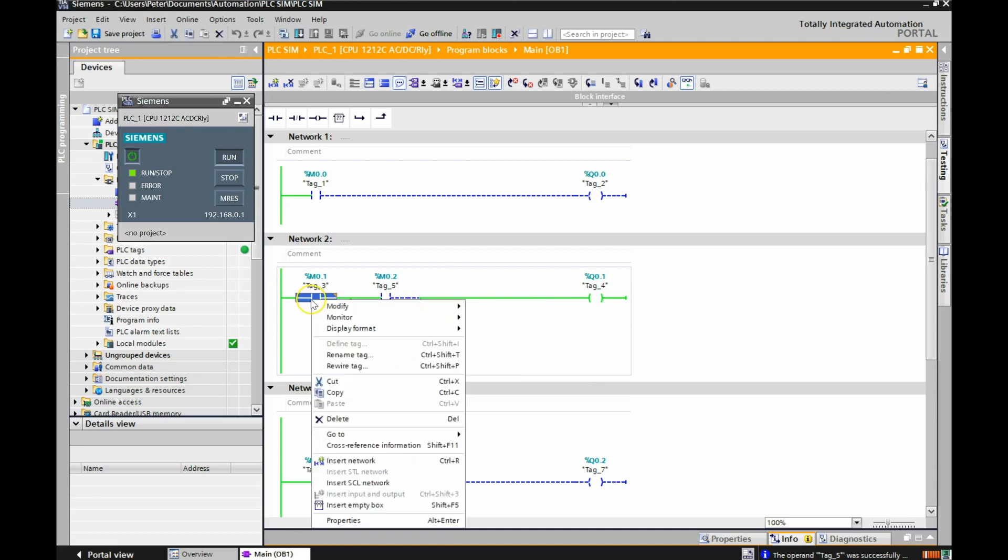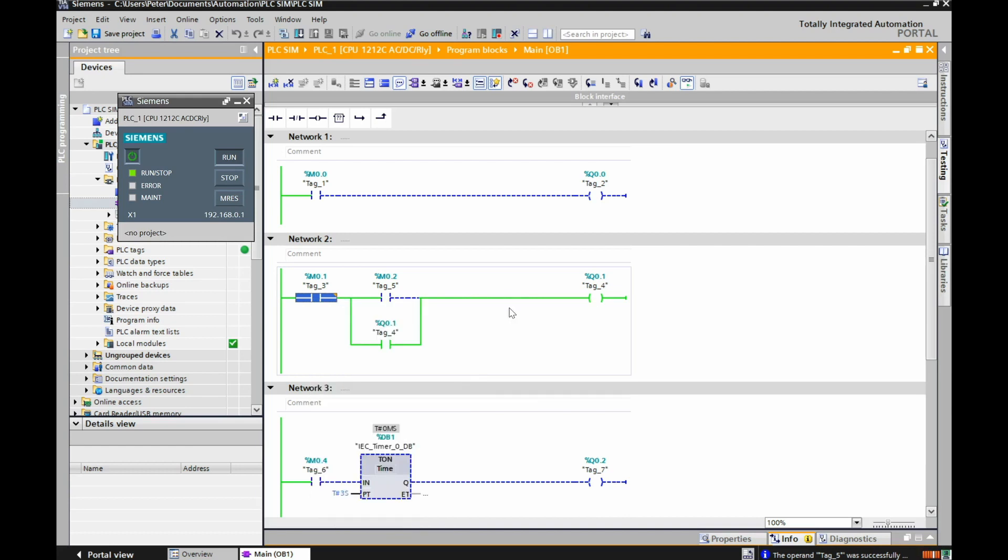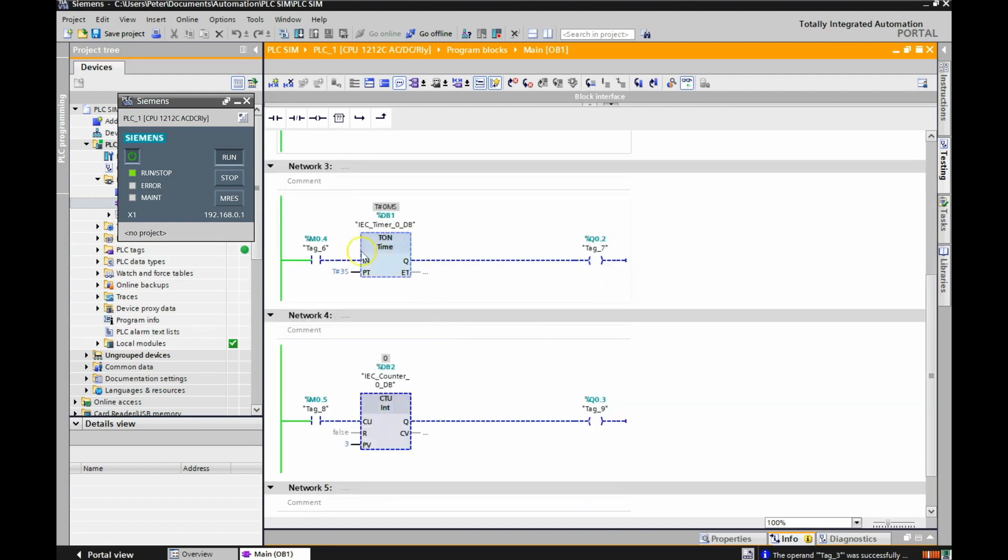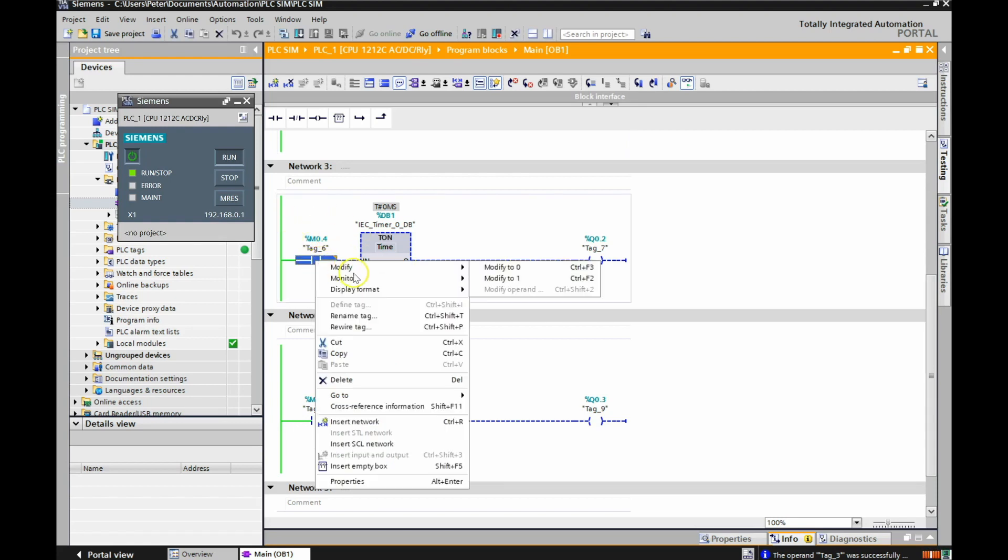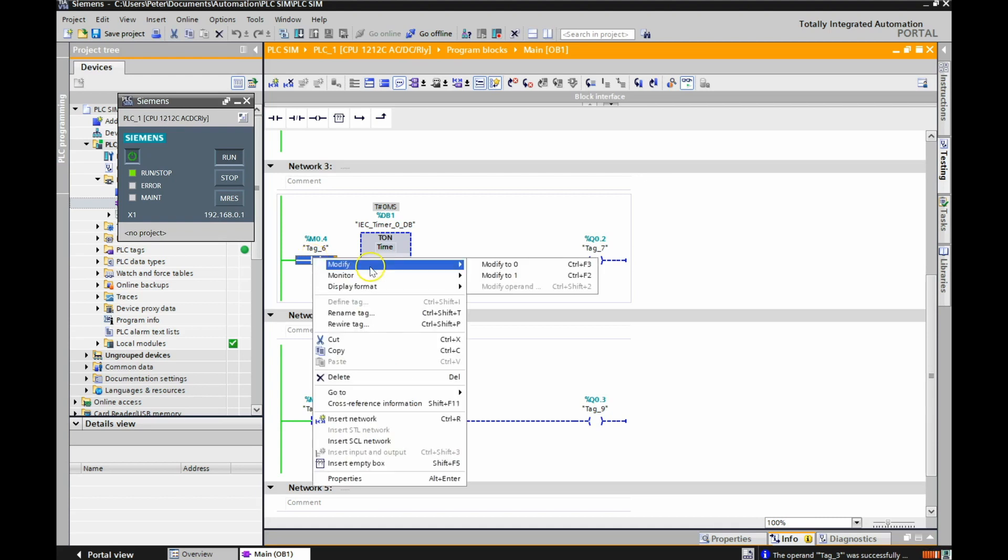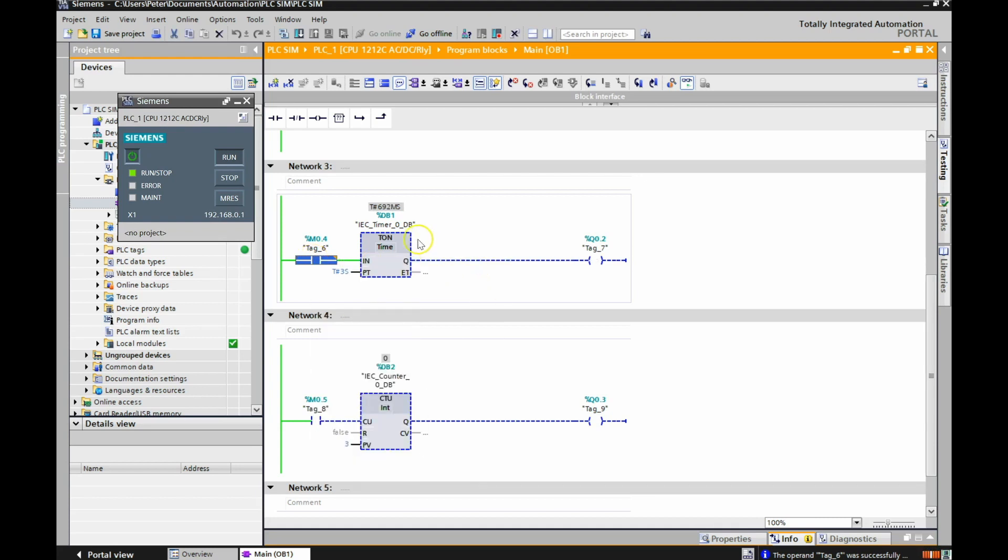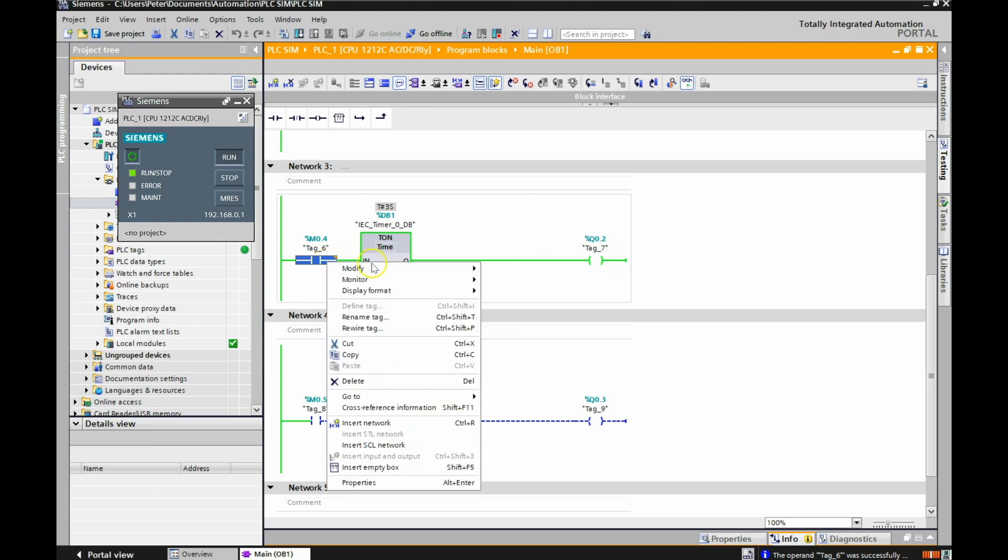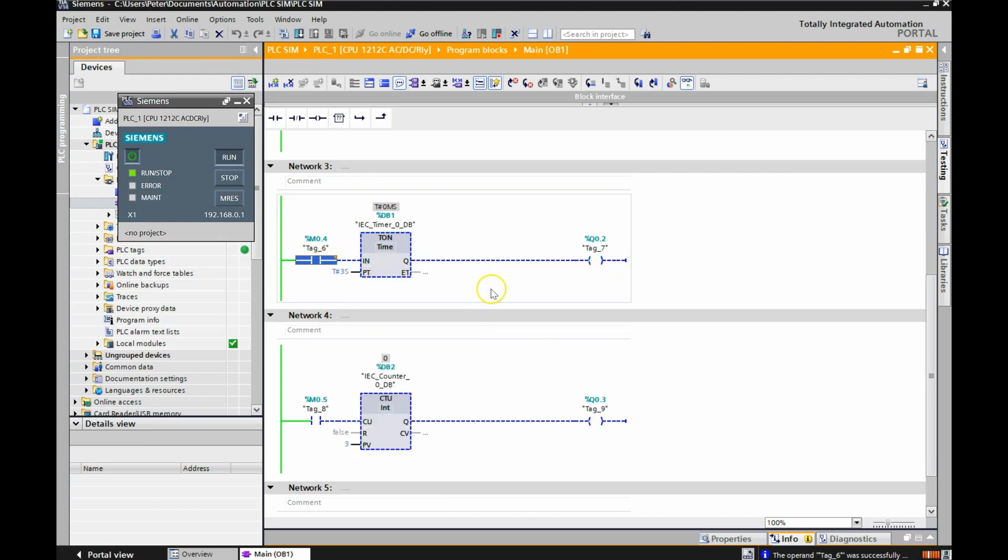If I now modify my Stop to a 0, then my Q0.1 should turn off. There we go. So a little bit of a lag, but not bad at all. Let's try the timer now. So I have an on-delay timer here. I have %M0.4, so I'm just using memory bits here. This looks like, what have I set this at? 3 seconds. So once I make this true, by modifying that to a 1, you'll see that the timer starts to time out. And then after 3 seconds, my Q0.2 should turn on. So I'll modify this to a 1. You can see this timing out to 3 seconds. At that point, the timer times out, and my Q0.2 has turned on. Beautiful. Let's modify this back to a 0. At that point, this is no longer true, so the output turns off exactly the same as we saw on our on-delay timer video. Very nice.